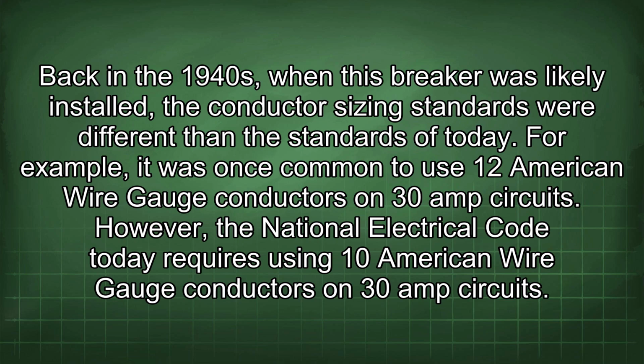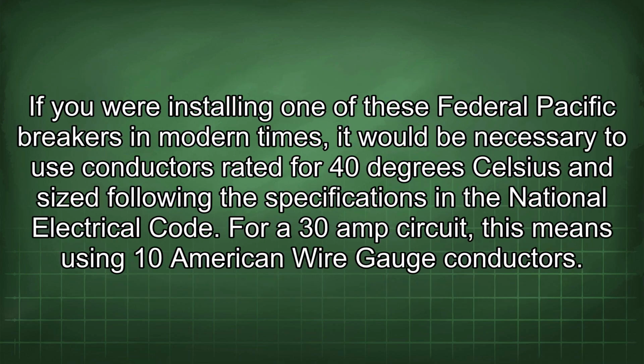However, the National Electrical Code today requires using 10 American wire gauge conductors on 30 amp circuits. If you were installing one of these Federal Pacific breakers in modern times, it would be necessary to use conductors rated for 40 degrees Celsius and size following the specifications in the National Electrical Code. For a 30 amp circuit, this means using 10 American wire gauge conductors.